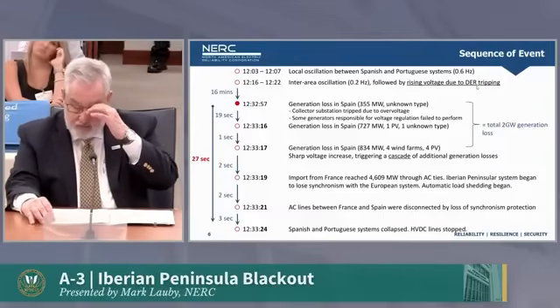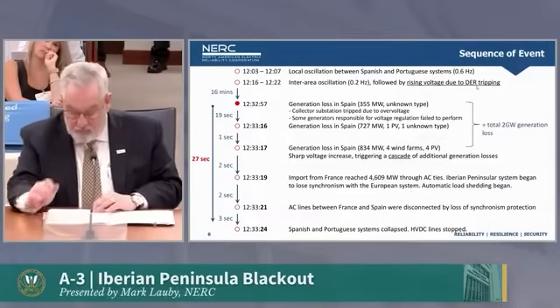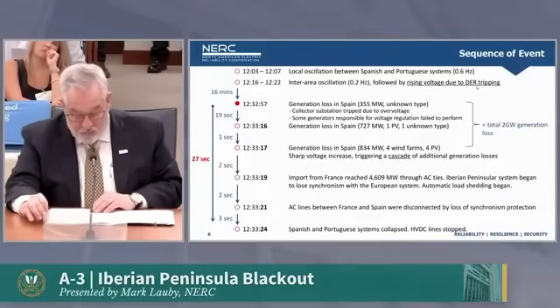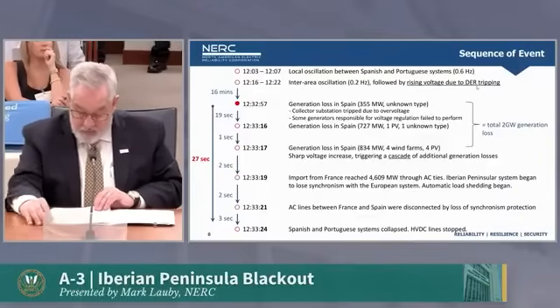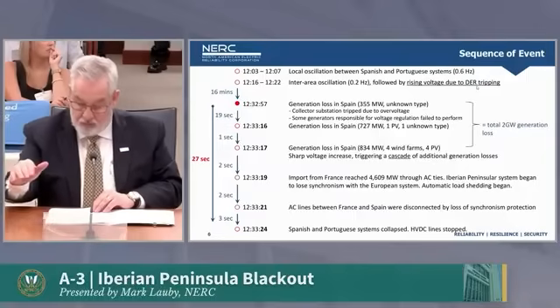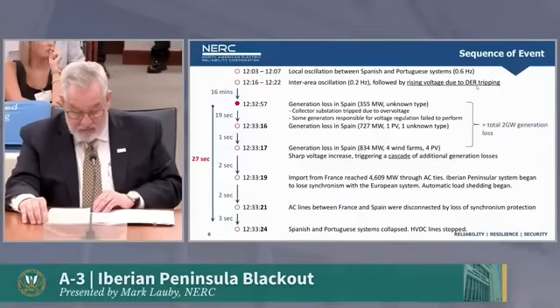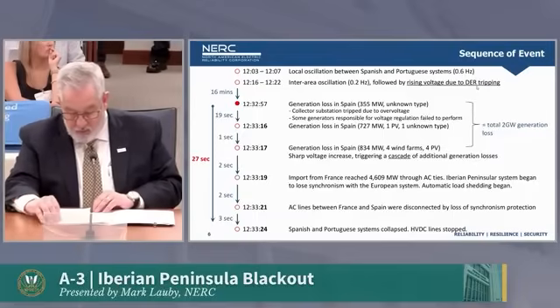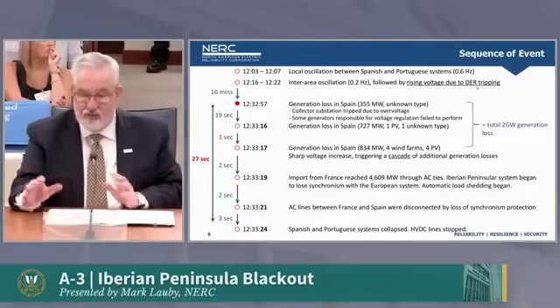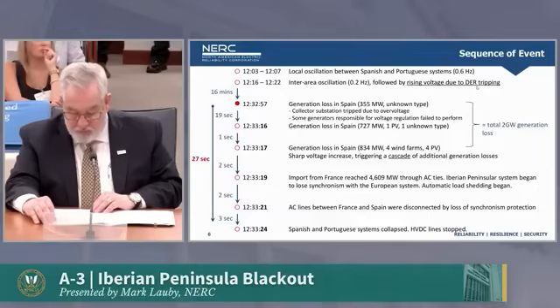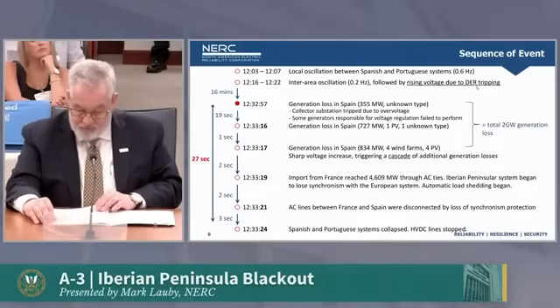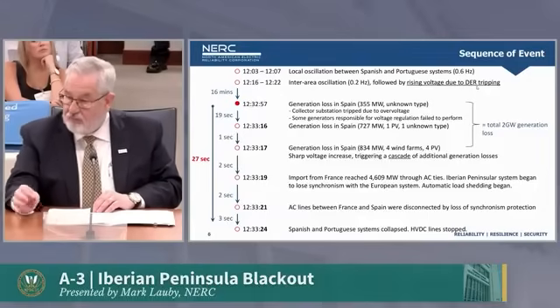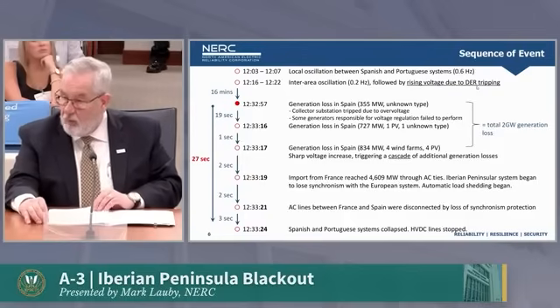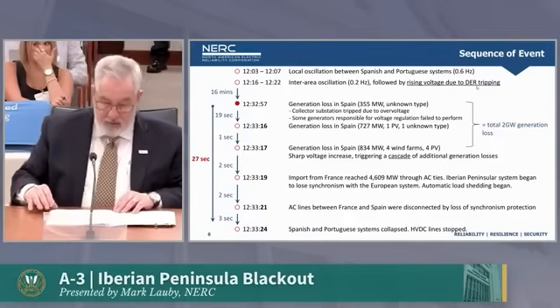In response to these oscillations, the operators activated mitigation measures. At 12:22, voltage levels began to rise. Ten minutes later, the first generation loss occurred. In the next 20 seconds, an additional 1.5 gigawatts was lost, involving a variety of different types of resources. The Spanish and Portuguese systems then collapsed within 27 seconds from the loss of the first generation - it happened very quickly, and there wasn't much operators could do.